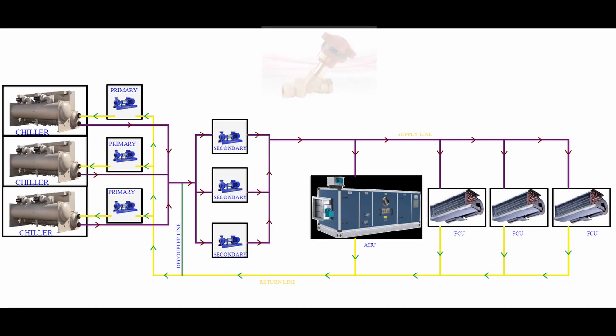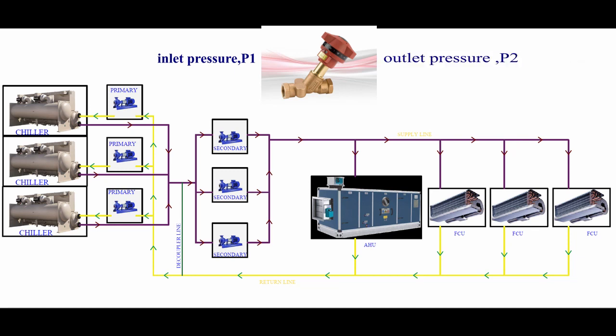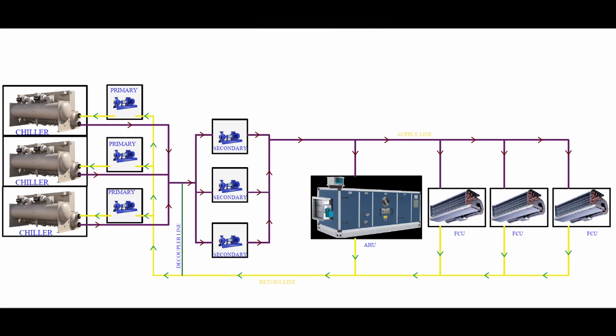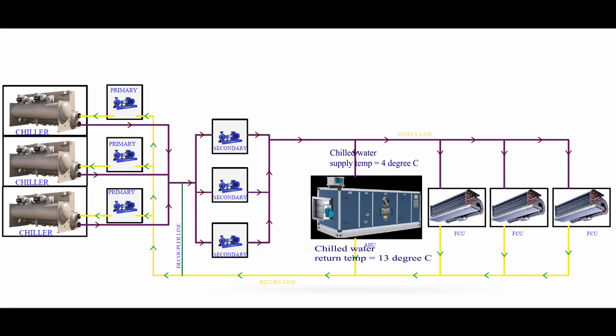Suppose we are using a double regulating valve for balancing — the flow rate through it will vary if any changes happen in its inlet or leaving pressure, that is the so-called differential pressure. At the time of water balancing, we calculate the differential pressure across the balancing valve and set the valve for the required flow rate using the valve manufacturer's data. But it is not a 100% balanced system — any changes in differential pressure cause a change in flow rate. This system has been designed with a delta T of 9°C. Consider this AHU: the inlet temperature is 4°C and leaving temperature is 13°C, so delta T is 9°C.